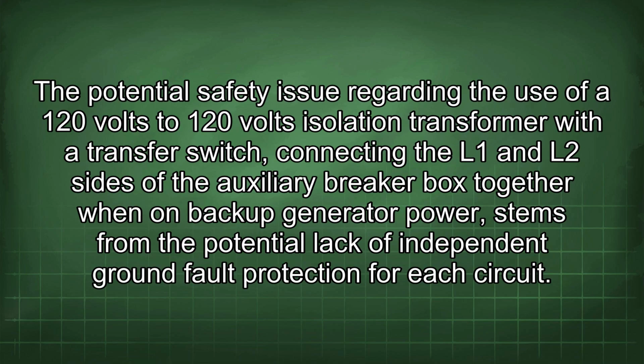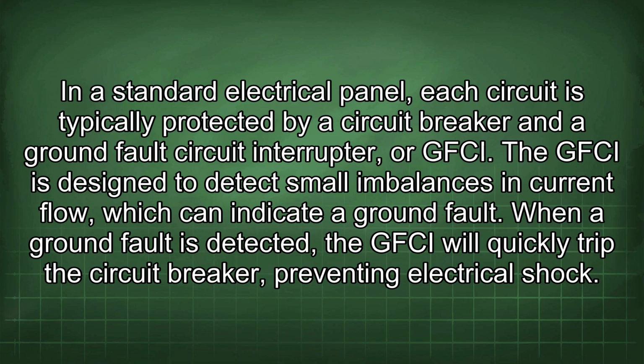The potential safety issue regarding the use of a 120 volts to 120 volts isolation transformer with a transfer switch connecting the L1 and L2 sides of the auxiliary breaker box together when on backup generator power stems from the potential lack of independent ground fault protection for each circuit. In a standard electrical panel, each circuit is typically protected by a circuit breaker and a ground fault circuit interrupter, or GFCI. The GFCI is designed to detect small imbalances in current flow, which can indicate a ground fault. When a ground fault is detected, the GFCI will quickly trip the circuit breaker, preventing electrical shock.